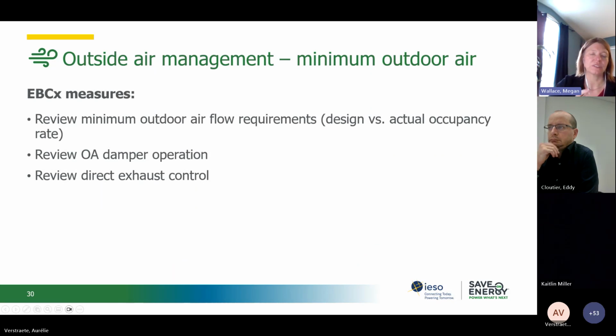To summarize, some of the measures that we were looking at were reviewing the minimum outdoor airflow requirements, the design requirements versus the actual occupancy rate, reviewing the outdoor air damper operation, and reviewing the direct exhaust control functions.